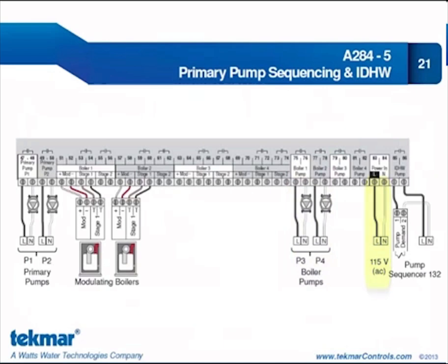And you can see here how we've connected the pump sequencer 132 to the IDHW pump terminals on the 284, so that contact closure to operate an indirect domestic hot water pump is being used to generate a pump demand on the 132.